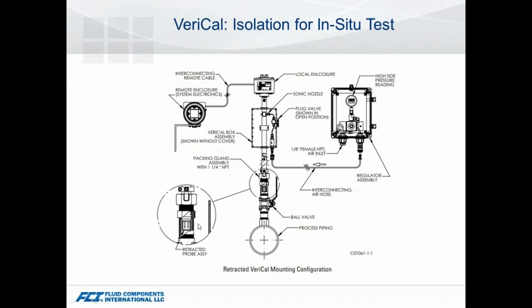A little bit more detail on that. When you go into this VeriCal mode, you need to be able to isolate it from the process, because we're going to be introducing a gas, and you can use nitrogen, compressed air, whatever gas you want. We use nitrogen at the factory as our baseline, but you can establish your own baseline off some other media from the day you install it. This gives you a feel for how it goes together: you isolate it, run your test, and compare it to your prior readings, just to give you that confidence. Again, it exercises the entire meter versus just the electronics.